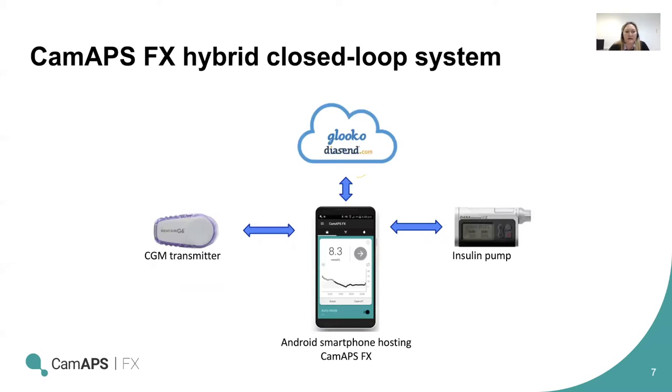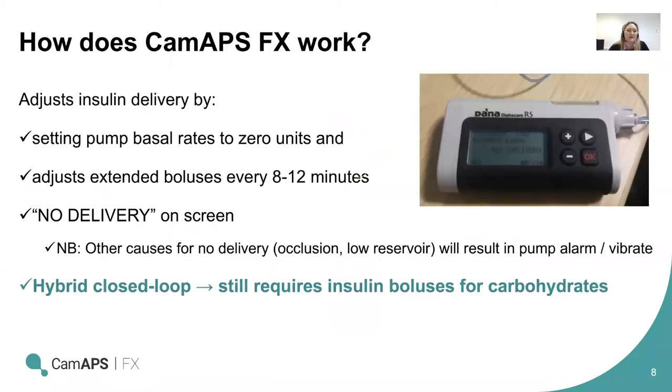Just a reminder of the system: CamAPS FX is a hybrid closed loop system. It is an app that runs on an Android smartphone and links via Bluetooth with a Dana insulin pump and a Dexcom G6 continuous glucose monitor. It sends data automatically to Diasend when attached to Wi-Fi or if there's a SIM card in the phone. The system adjusts insulin delivery by turning off the pump's normal basal rates and setting those to zero — it will flash 'no delivery' on the screen. It then delivers an extended bolus every 8 to 12 minutes depending on the glucose level.